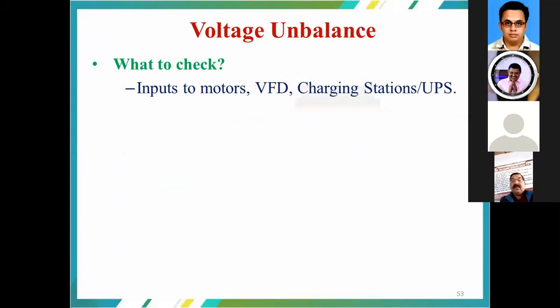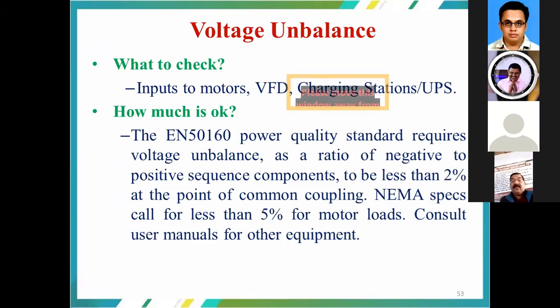And voltage unbalance we can check at the input to the motors, the variable frequency drives, charging stations or the UPS. As far as the EN 50160 power quality standard is concerned, it should be less than 2%. And as per NEMA specifications, it is less than 5% for motor loads. And for the specific range of voltage unbalance, we are supposed to refer to the manuals of the equipment or devices.